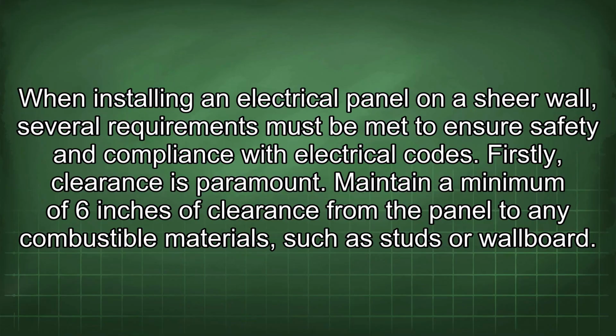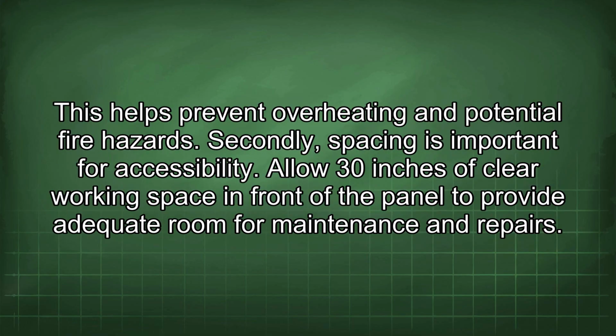When installing an electrical panel on a shear wall, several requirements must be met to ensure safety and compliance with the electrical codes. Firstly, clearance is paramount. Maintain a minimum of 6 inches of clearance from the panel to any combustible materials, such as studs or wallboard. This helps prevent overheating and potential fire hazards.